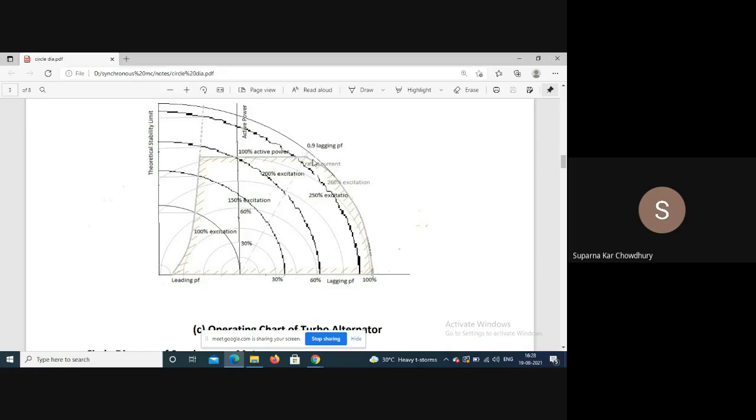Beyond the rated power factor line, the power output is dictated by the current rating of the machine. Corresponding to 100% active power and rated current, this segment is part of a circle corresponding to rated current, with center at the origin.